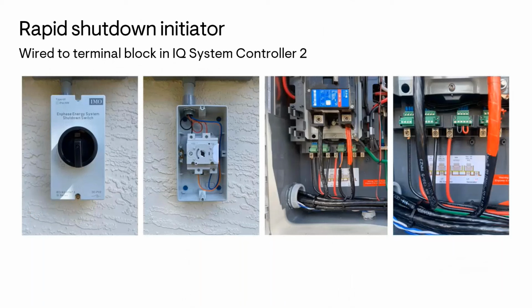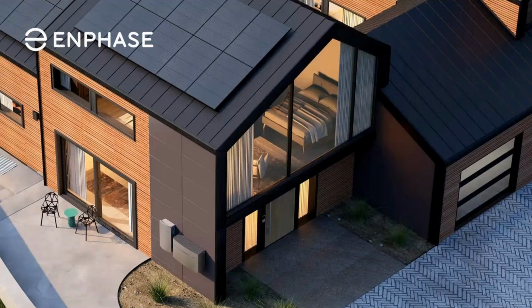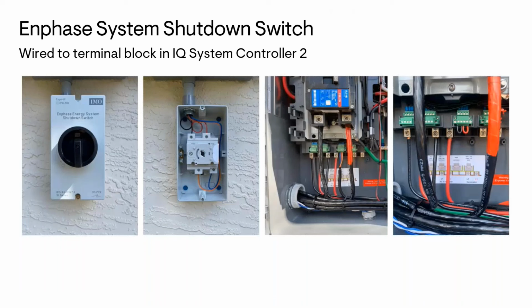Okay, here I've got a few pictures which depict the rapid shutdown initiator and how it's connected to the system controller. And I just realized that I'm going to put the correct name here so you recognize it from our ADLP and spec sheets and stuff. It's called the Enphase System Shutdown Switch. Okay, so it's actually made by IMO for Enphase. The Enphase brand is on there if you get the Enphase supplied one, but the IMO model is exactly the same and can be used.